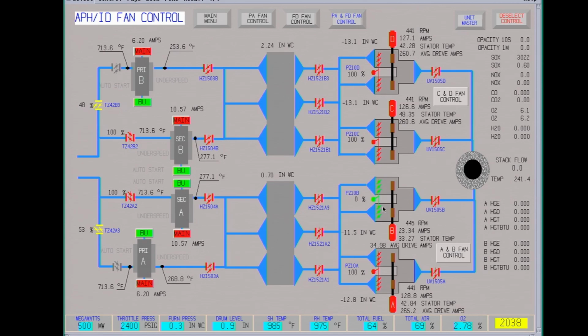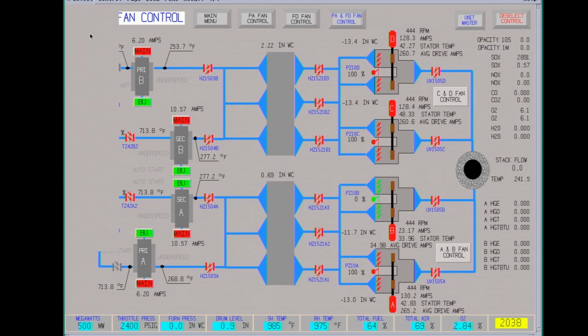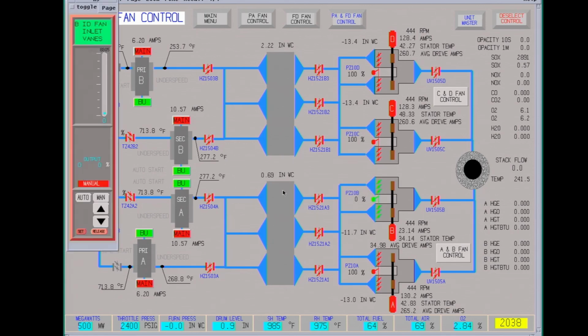Now the big thing with this, when you put this in service, when you start opening the inlet damper, it could pick up any dust in the ducts, and it's going to give you an opacity exceedance. You could get high opacity. So we're going to start by opening it really slow. And when we do this, we'll have to watch the opacity. That's up here.